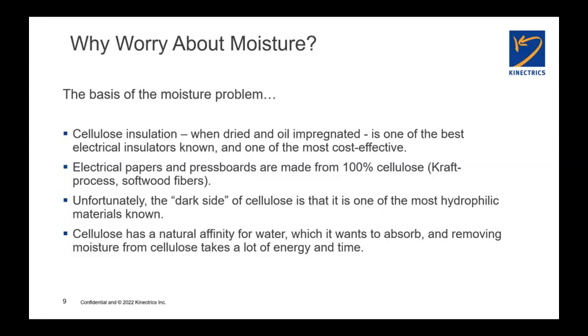And as good as cellulose is as an insulation material, its dark side, as I like to call it, is that it is one of the most hydrophilic materials known. It wants to absorb and attach itself to water, or conversely, water attaching itself to the cellulose. And it is extremely difficult in terms of time and energy to separate that moisture from the cellulose insulation. And so that causes the basis of the problem.